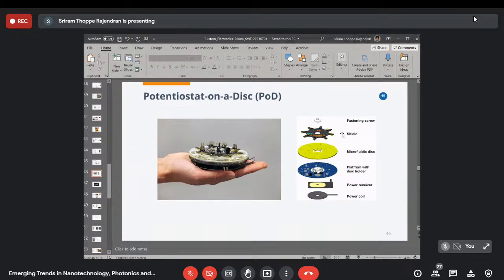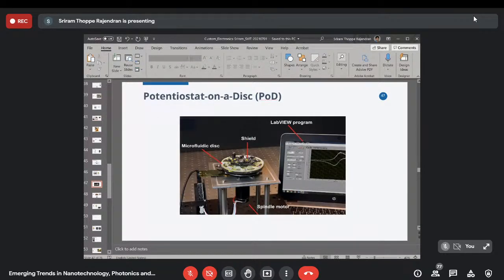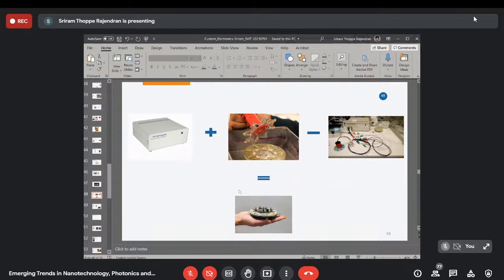Then we have the shield, where we have the connections to the electrode. You can see these spring-loaded gold pins. They sit right on top of the electrode and spin along. It's so well integrated and connected that we won't get much noise. That's how the device looks: a shield placed on top of the electrode, and then we have a LabVIEW program to control the device. The LabVIEW program has been done very elegantly by one of our students in the lab. So what does our device do? Our device is basically a potentiostat with the ability to rotate with the disk, but without wires. We eliminated the wires, and that's how the final product looks. It's so small, very elegant, and works all the time.